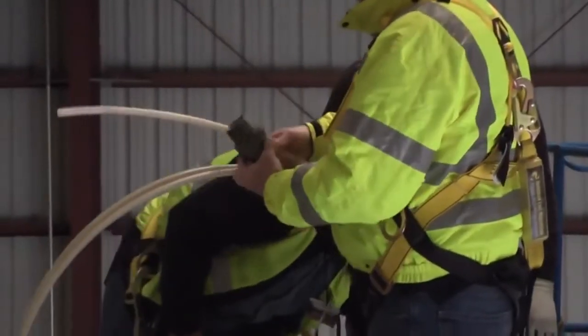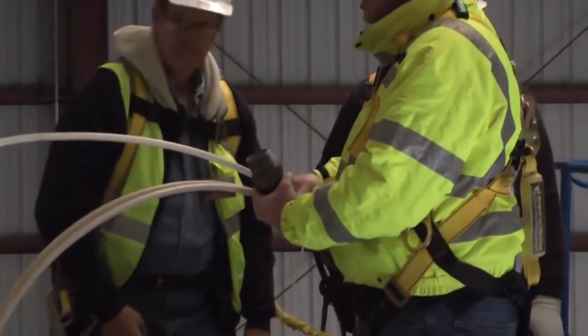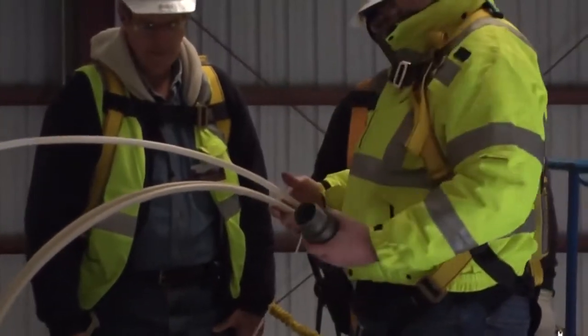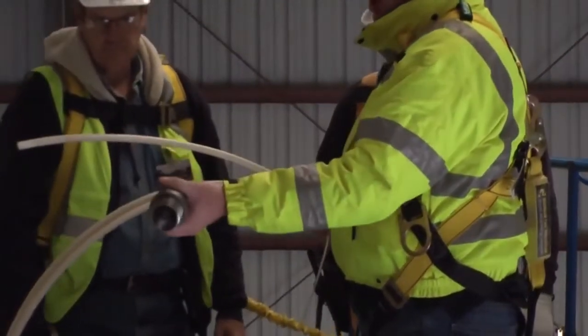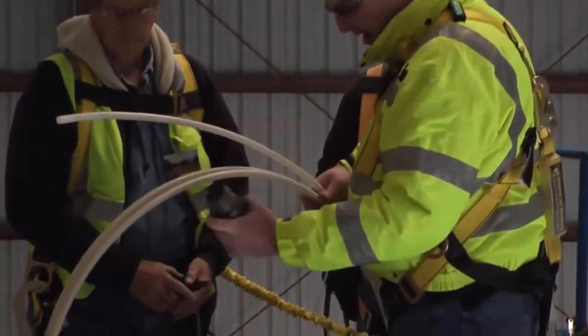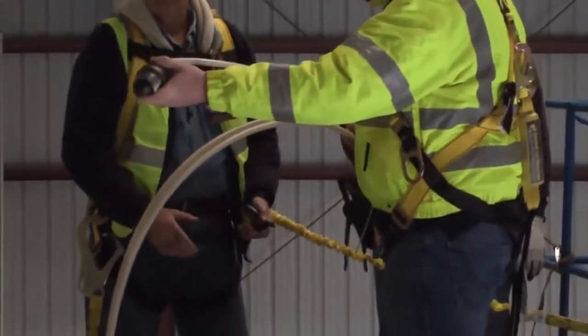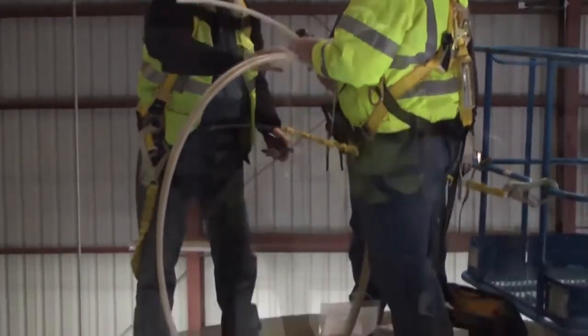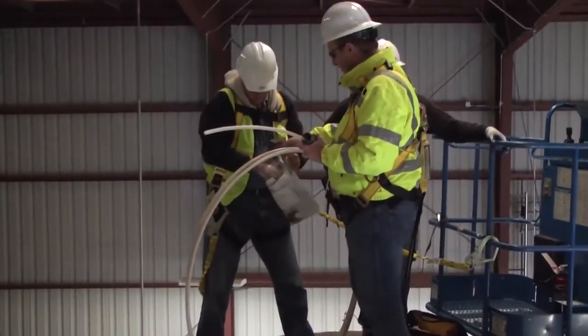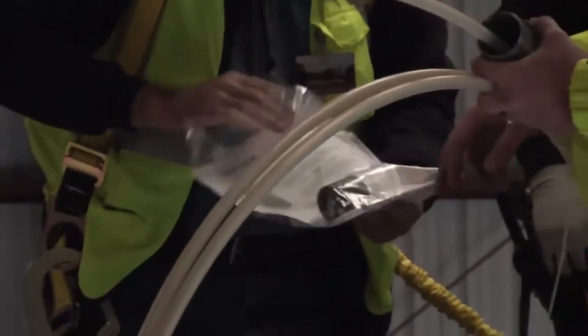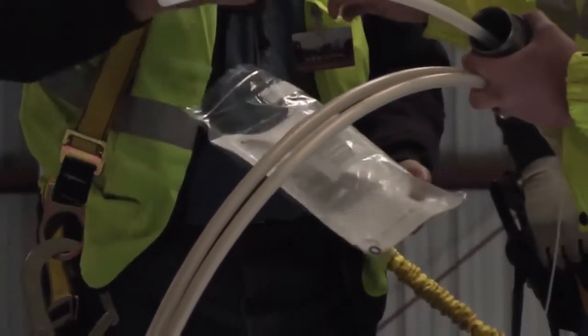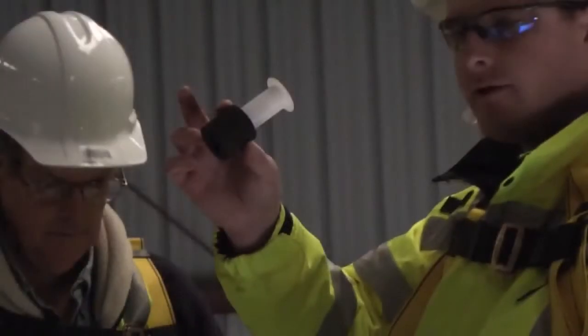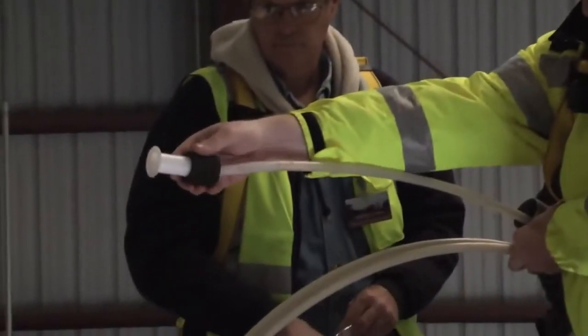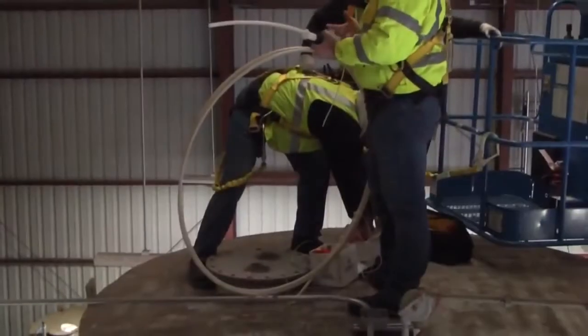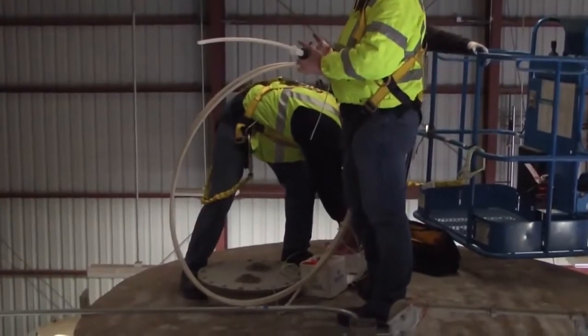Now cut only the first wire tie in order to assemble the hardware on the end of the probe. Because this is a shorter length probe, you want to make sure that you have room to slide your fitting on. Make sure you slide it on so it's going to end up right side up. So we'll slide that on first. When they send you the probe kit, it's going to have spacers and everything. The only thing you really need is the float itself. And you want the magnet to be closest to the product, because that's where the reading is going to come from. And you want a spacer between the magnet and the weights. So we're going to slide this on so it looks like it's going on upside down.